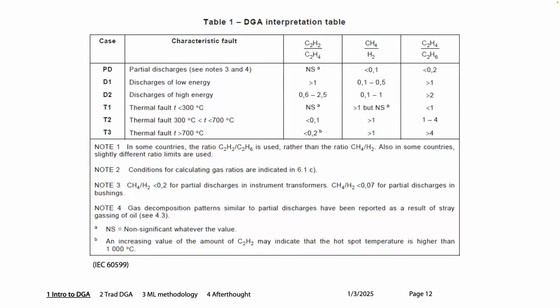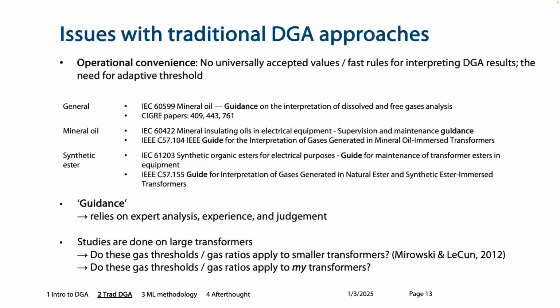Actually, the standard is quite poorly written, and it's difficult to do the diagnosis, to be honest. How difficult is it? The first thing is that it's not very convenient to do the diagnosis directly, because there is no universally accepted approach to do DGA. The IEC standard is one thing, but if you go to the American standard, we call that the IEEE standard. They have another set of rules or approach of interpretation. So which one should you rely on?